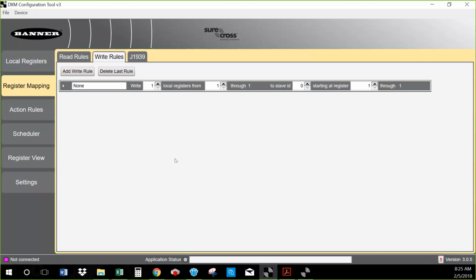And again, I've told you guys in the last session, you have to think of this DXM100 as actually multiple things. So you have a gateway, which is one thing. You have the controller section, or the PLC, if you will. That's another thing. You have a board in the back that has your built-in I/O, and that's another thing. And then you have the LCD, which is actually another thing.